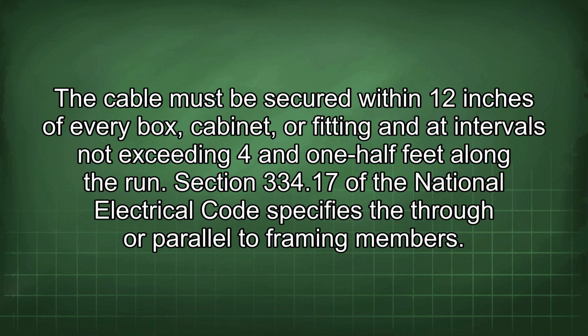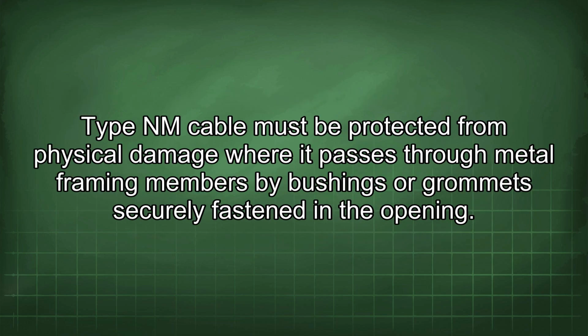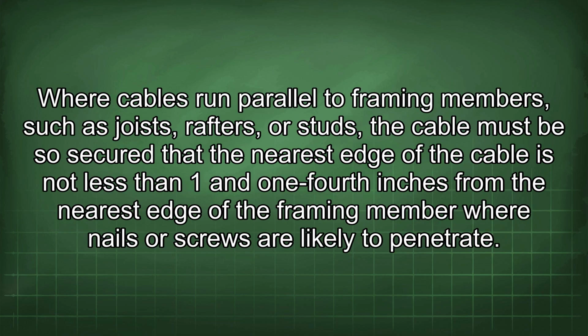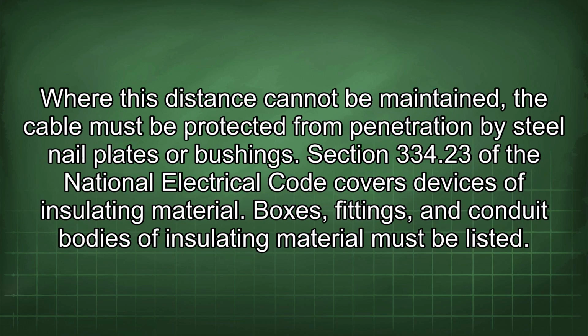Section 334.17 of the National Electrical Code specifies the requirements for running cable through or parallel to framing members. Type NM cable must be protected from physical damage where it passes through metal framing members by bushings or grommets securely fastened in the opening. Where cables run parallel to framing members, such as joists, rafters, or studs, the cable must be so secured that the nearest edge of the cable is not less than 1 1/4 inches from the nearest edge of the framing member where nails or screws are likely to penetrate. Where this distance cannot be maintained, the cable must be protected from penetration by steel nail plates or bushings.